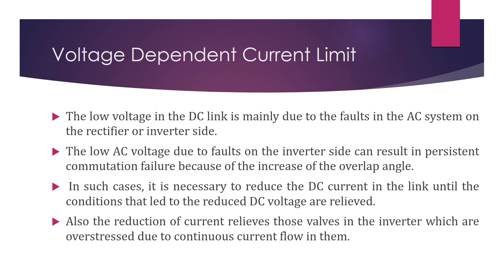The next topic is voltage dependent current limit. The low voltage in the DC link is mainly due to fault in the AC system on the rectifier or inverter side. Low AC voltage due to fault on the inverter side can result in commutation failure because of an increase in overlap angle. In such cases, it is necessary to reduce the DC current in the link.